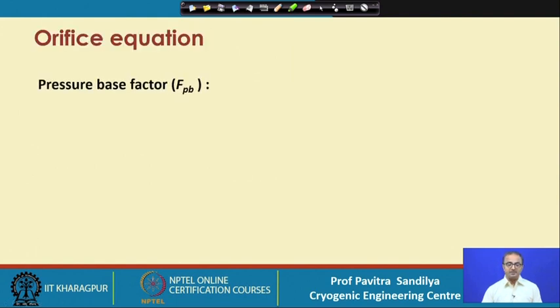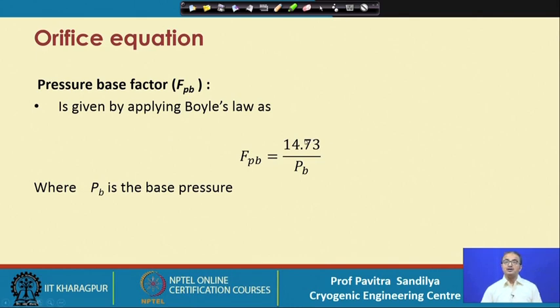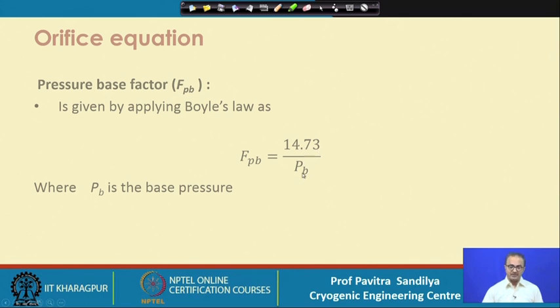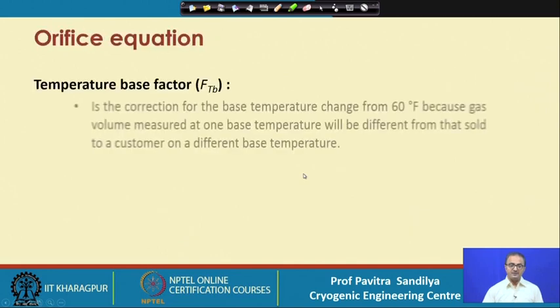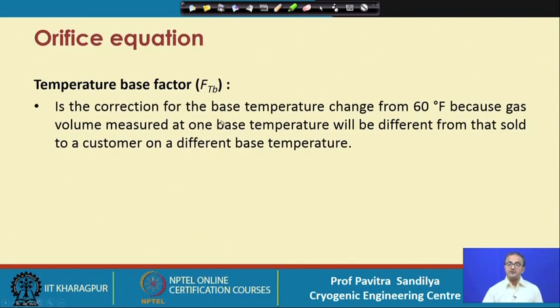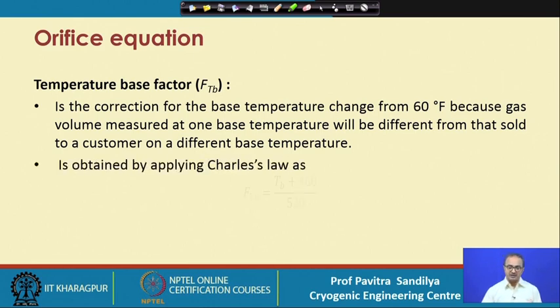The pressure base factor applies to the change in volume due to pressure change, using some base pressure. The temperature base factor corrects for the base temperature when it differs from 60°F (about 15°C), because gas volume changes with temperature. This correction is obtained using Charles' Law with 520 Rankine as the reference, and Tb is expressed in Rankine — though it can equivalently be expressed in Kelvin.